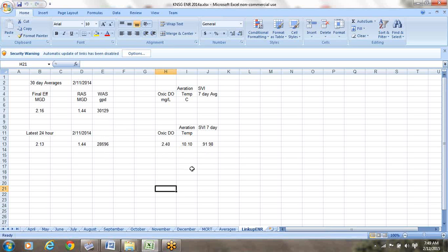Now, the plant updates these sheets every day. So as long as you update the sheet, let's say at 10 in the morning, and IViewOps is on auto run to import at noon, it will pick up the latest 24-hour value automatically from the sheet, and you do not have to do anything other than what you were doing routinely, just keep updating the sheet. Now, we do have protocols if for some reason your operator is ill and you do not update the sheet, then IViewOps does not revert to some crazy number. It defaults to certain intelligent numbers, which is part of the IP around how we handle not only just flows but set points, etc.